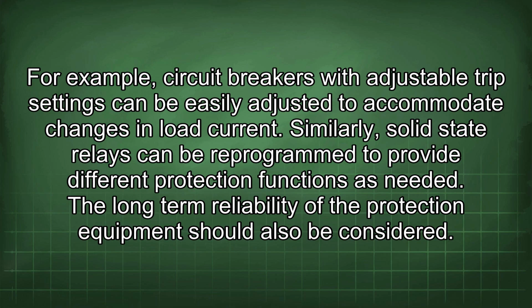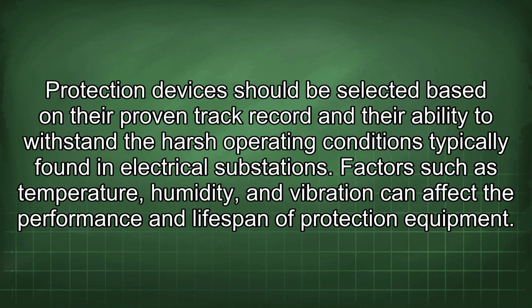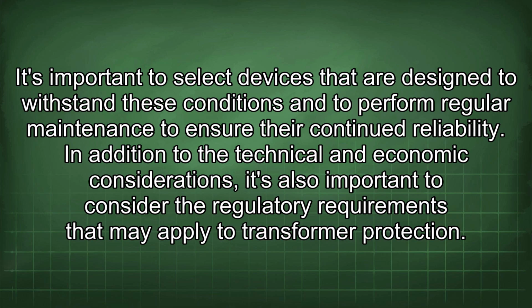The long-term reliability of the protection equipment should also be considered. Protection devices should be selected based on their proven track record and their ability to withstand the harsh operating conditions typically found in electrical substations. Factors such as temperature, humidity, and vibration can affect the performance and lifespan of protection equipment. It's important to select devices that are designed to withstand these conditions and to perform regular maintenance to ensure their continued reliability.